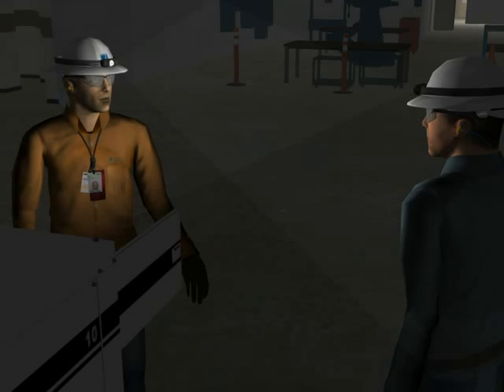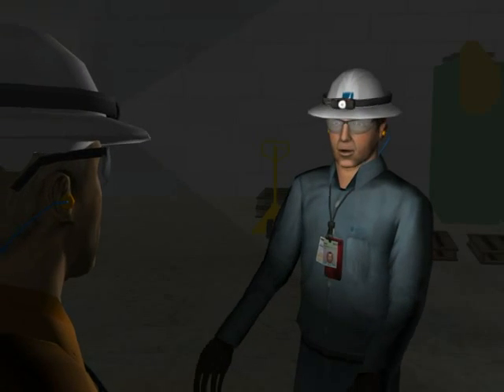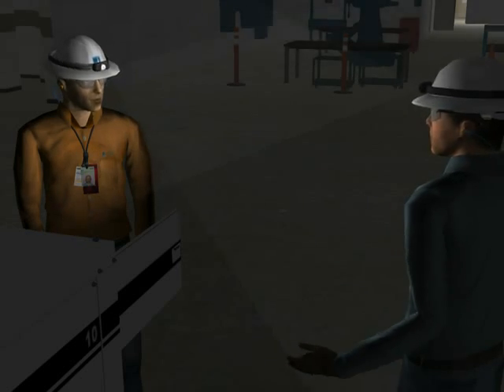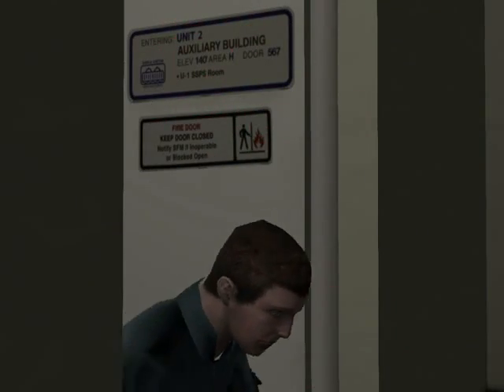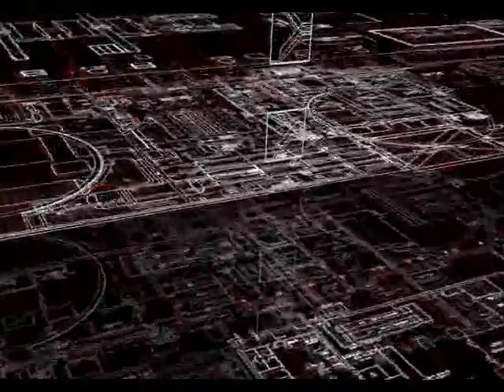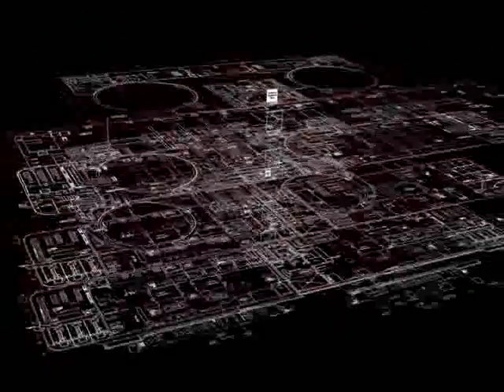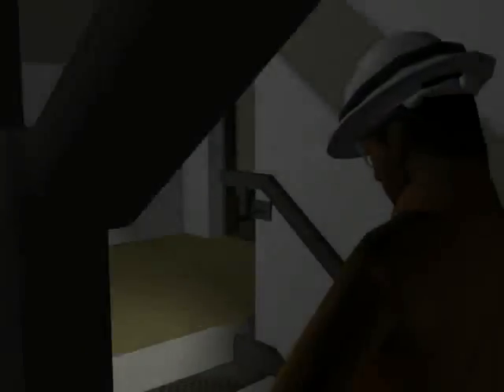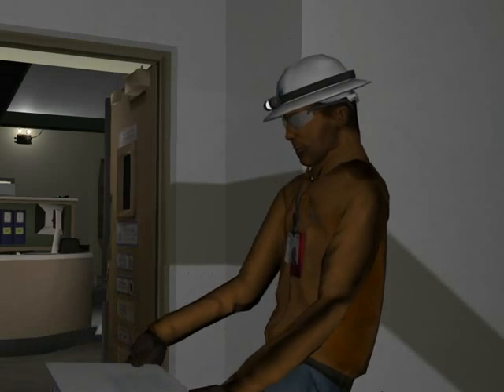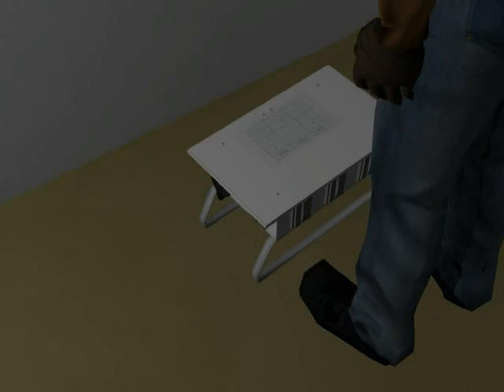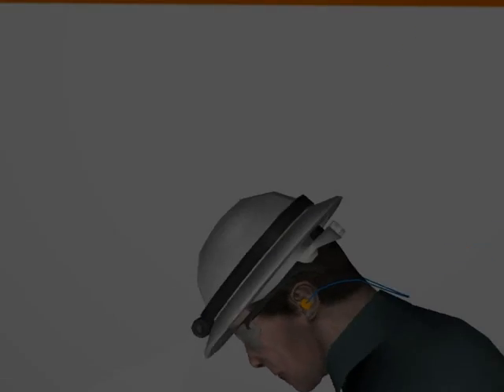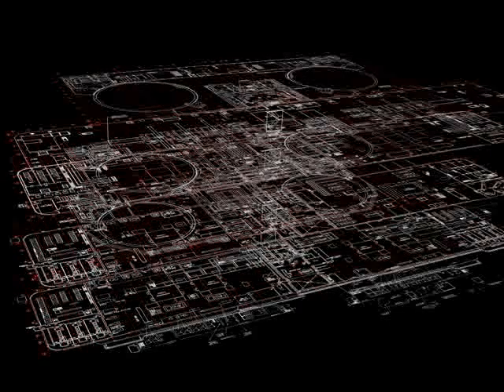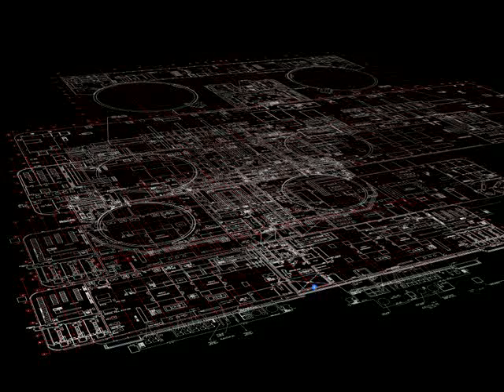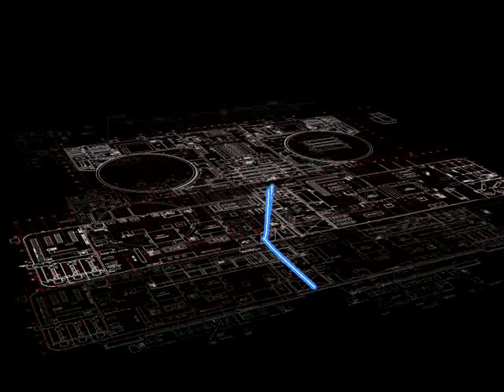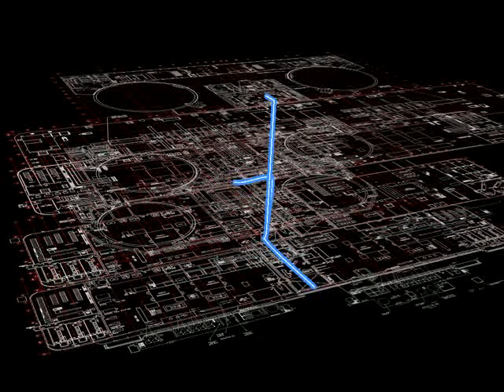I'll finish setting up the generator. You set up the temporary distribution panels. Understand. I'll set up the temporary distribution panels. Correct. Temporary distribution panels are deployed at staging locations for the control room and battery charger inverter rooms to support the fans in these areas. 240-volt cables are routed from the generator staging location through the machine shop, up the stairwell to the staged temporary distribution panels.